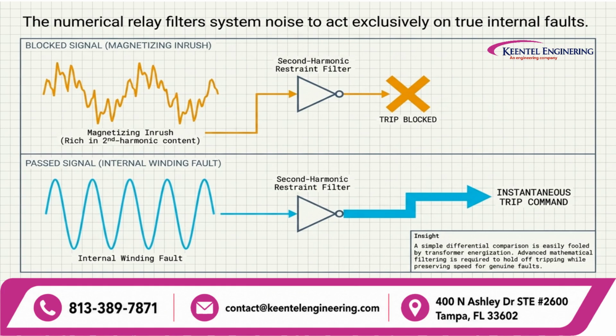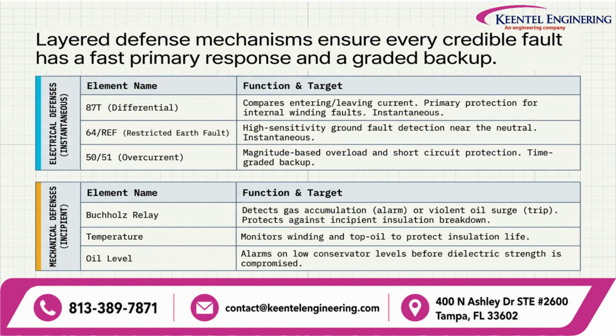Now, compare that with an internal winding fault. A genuine internal fault produces a different current signature. The relay's filtering logic recognizes that the signal does not match the expected inrush characteristics. The restraint is therefore not applied in the same way, allowing the relay to issue an instantaneous trip command. The engineering objective is to achieve both security and speed. We want the relay to remain restrained when the transformer is being energized, while still responding extremely quickly when an actual internal fault occurs. A reliable transformer protection system uses layered defense mechanisms.